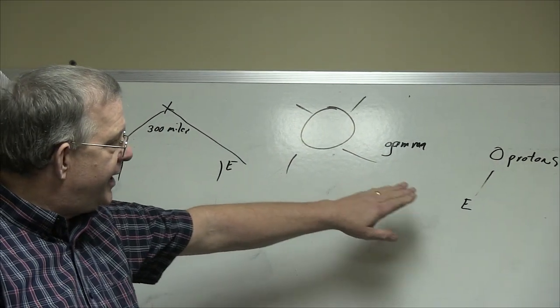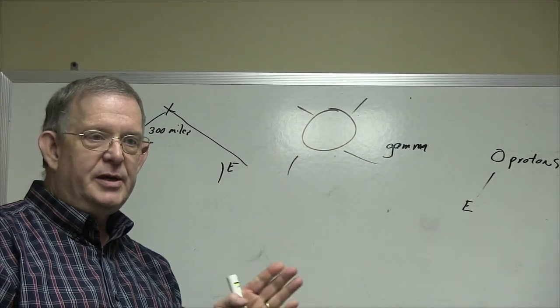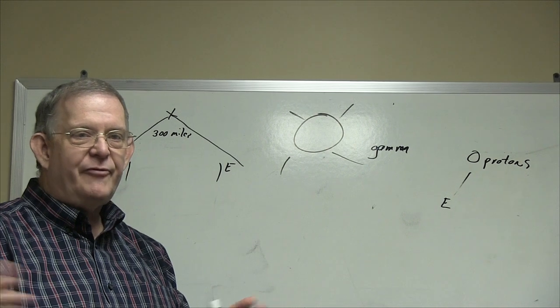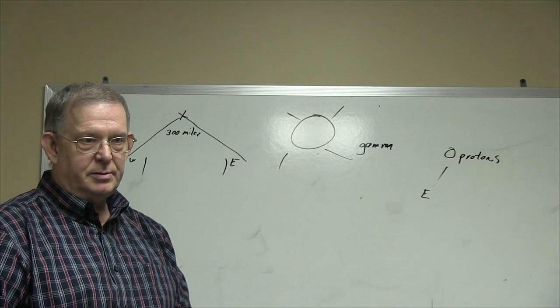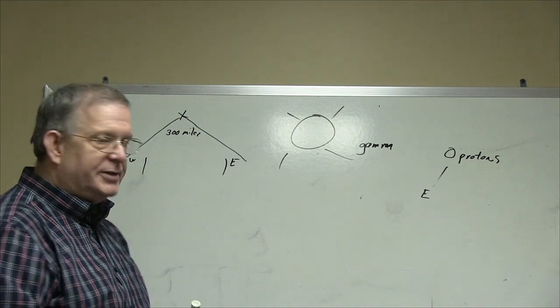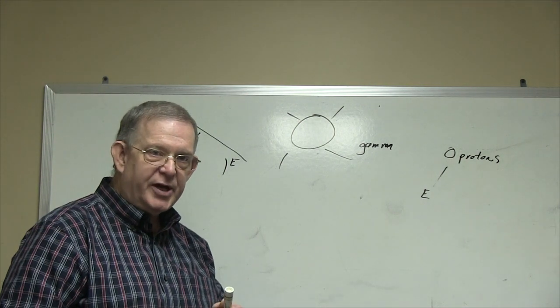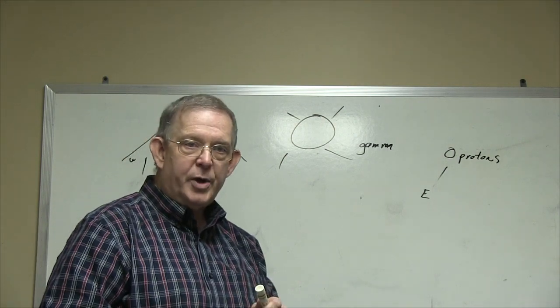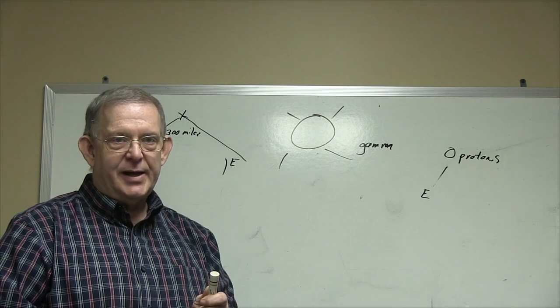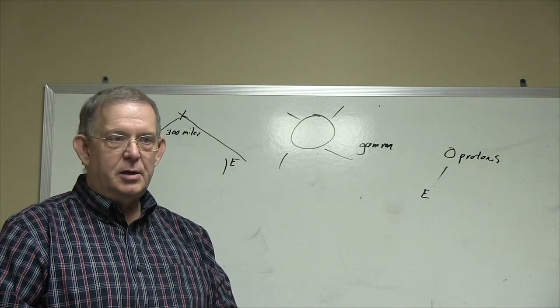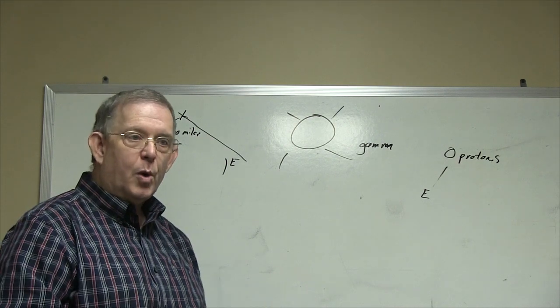The gamma rays hitting the protons, all of this happens between five and five hundred billionths of a second. It's very fast. That's why our device has to, under military specifications MIL standard 188.125.1, be able to take that spike and shunt it within 20 nanoseconds. We're way below that.